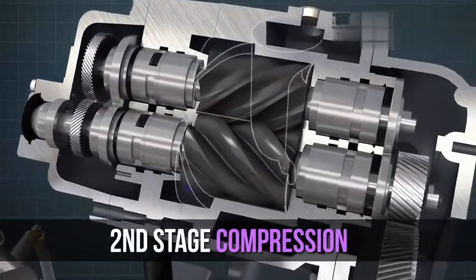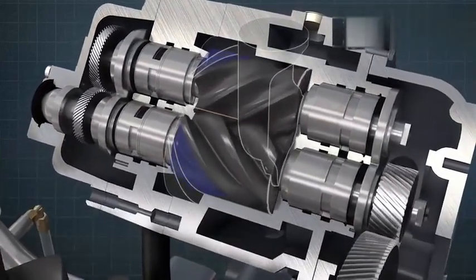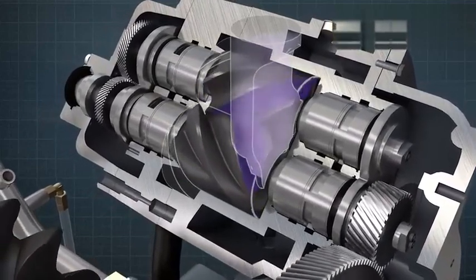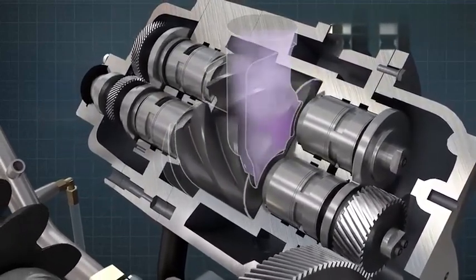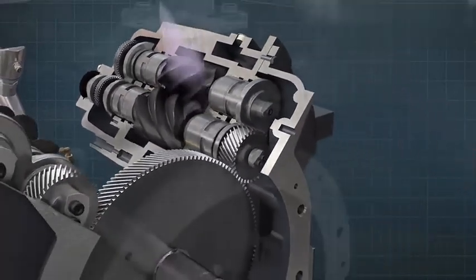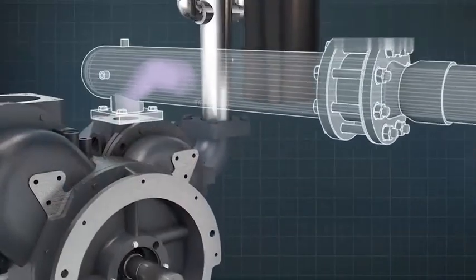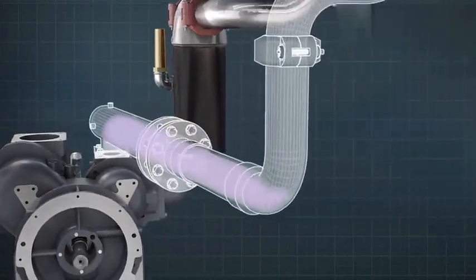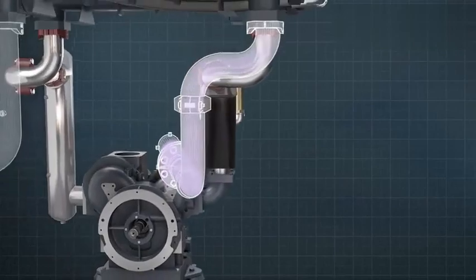The second stage further compresses the air to the required pressure in the same manner as the first stage. However, this time, the compression process takes place on the upper side of the rotors. The compressed air exits the air end via a delivery silencer, then through a non-return valve. The air then passes through a final second stage air or water cooler.